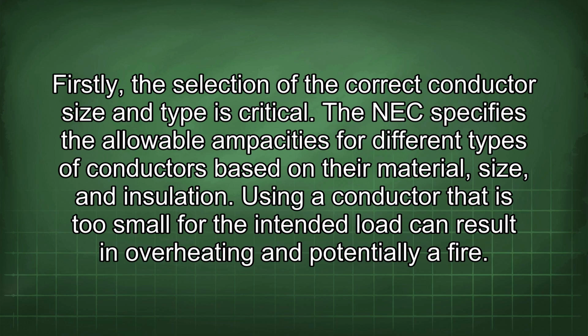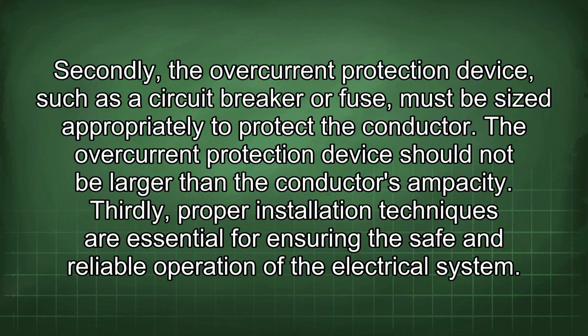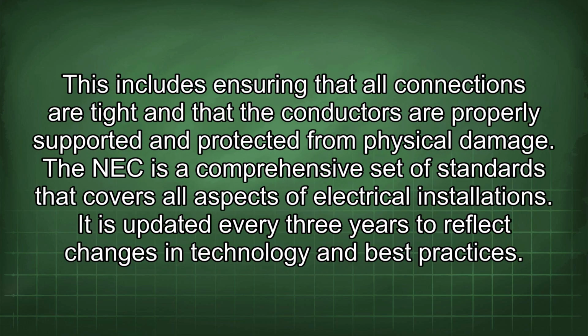Firstly, the selection of the correct conductor size and type is critical. The NEC specifies the allowable ampacities for different types of conductors based on their material, size, and insulation. Using a conductor that is too small for the intended load can result in overheating and potentially a fire. Secondly, the overcurrent protection device, such as a circuit breaker or fuse, must be sized appropriately to protect the conductor. The overcurrent protection device should not be larger than the conductor's ampacity. Thirdly, proper installation techniques are essential for ensuring the safe and reliable operation of the electrical system. This includes ensuring that all connections are tight and that the conductors are properly supported and protected from physical damage.